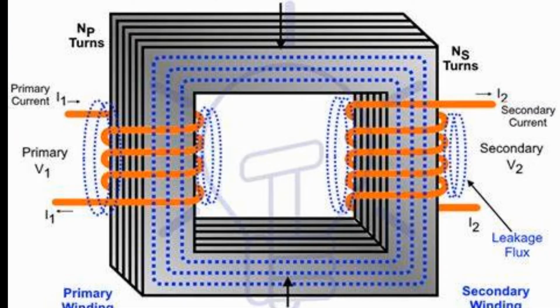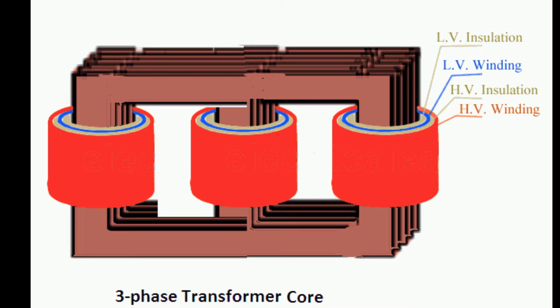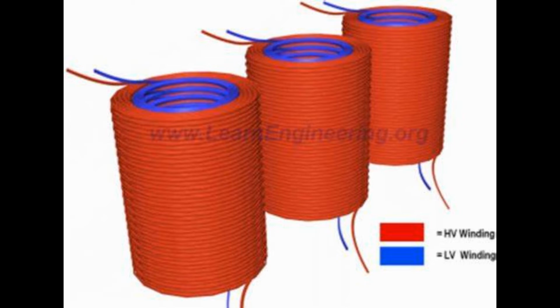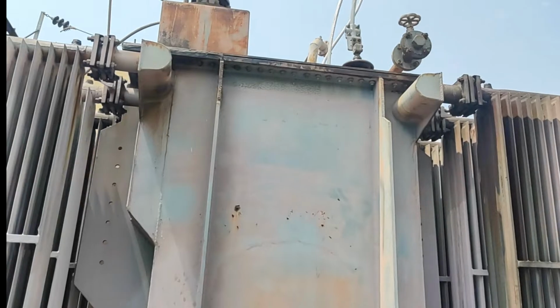A transformer consists of at least two windings, the primary and the secondary. The primary winding is the winding in which the input voltage is applied, while the secondary winding is the winding that receives the output voltage. The primary and the secondary winding of the transformer can play as the high voltage HV winding or the low voltage LV winding. The HV winding has a greater number of turns and consists of a thinner conductor than the LV winding. The LV winding, the low voltage winding, has fewer turns. It consists of a thicker conductor than the HV winding, since higher current is carried in the LV winding. Both the HV and LV windings are separated with proper insulating material and placed in a main tank filled with cooling oil. So now let us discuss the parts of the transformer in detail.